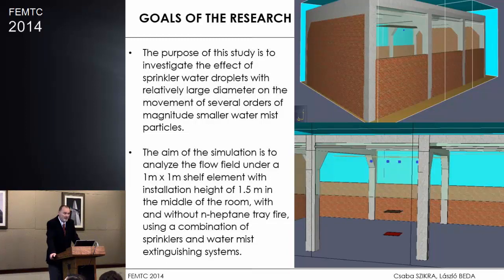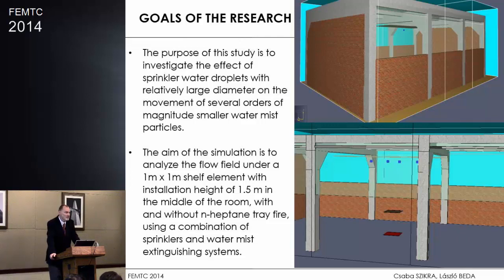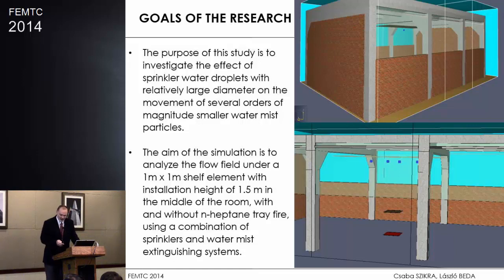We know that sprinkler and water mist systems work in totally different ways. The average droplet size of a sprinkler is around one millimeter, and for the water mist system, 99% of the droplets are less than one millimeter. When we started the simulation, we didn't even know whether it was possible to simulate it or whether we'd get realistic results using FDS. But we got some results finally.